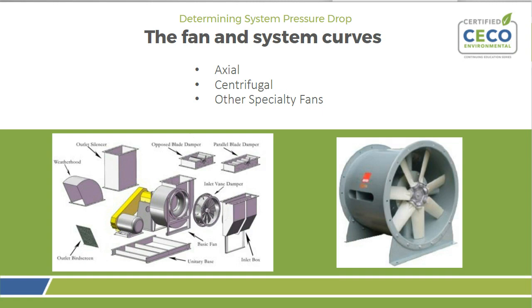The fan. There are 2 types of fans, axial on the right and centrifugal on the left. In most industrial ventilation systems, we're going to be using that centrifugal fan. Axial fans you can use possibly in the return air line if it's a long run, if you're sending the air back into the plant or to another location. In the diagram at the bottom left, there's an inlet box shown. Those are good accessories to purchase with your fan because they replace the 90-degree elbow. In most cases, the fan is on the ground. The duct from the collector or collection device is coming down.